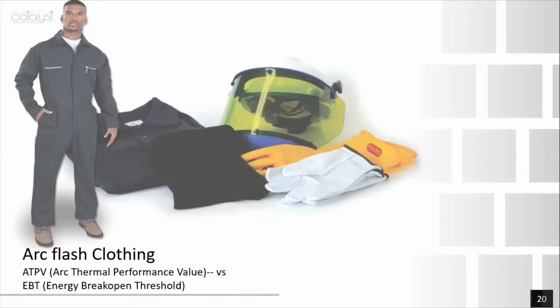When you see the ATPV on a tag, it'll be in calories per centimeter squared. We're going to go over what calories are in a moment, but all good clothing is going to have an ATPV. The next one down, EBT, the energy break open threshold, is the incident energy on a material that results in a 50% probability of break open. That's defined as an area of at least 1.6 square centimeters. So they actually blast the clothes until they blow apart.